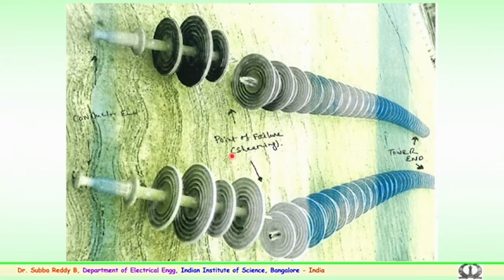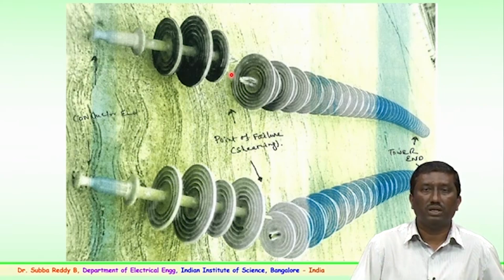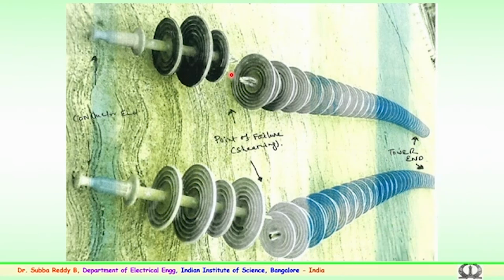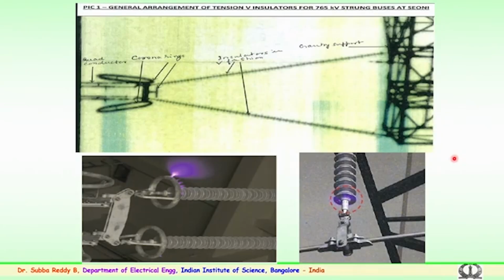These are again various failures which have been noticed over a period of time in the polymer insulator. This is particularly for one of the transmission systems, a 765 kV line, where the tower failure happened 8 to 9 months after the erection. So, a very serious concern. The technology which you are adopting has to be carefully looked at, so that equal importance is given not only to the material and the newer technology, but also to how it is being used, how it is being erected in the field, and what the orientation of the corona control rings is. This failure was due to the placement, design and orientation of the corona control rings.